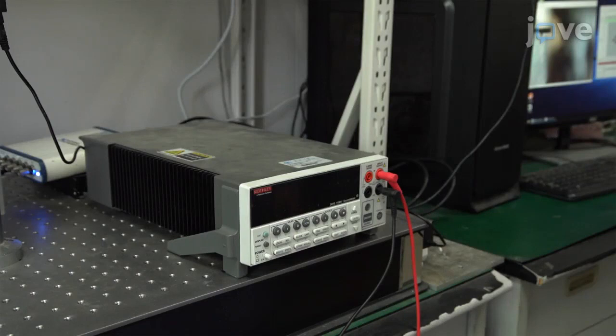After measuring the capacitance gradient, use a computer-controlled DC power supply to calibrate the optical lever. This schematic provides an overview of the setup for calibration.